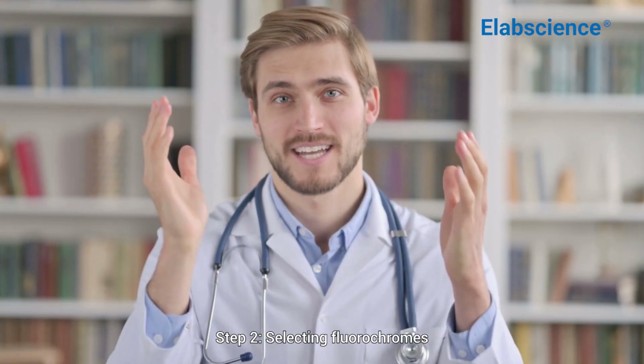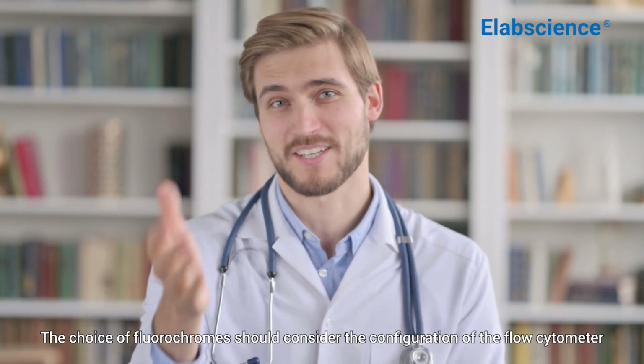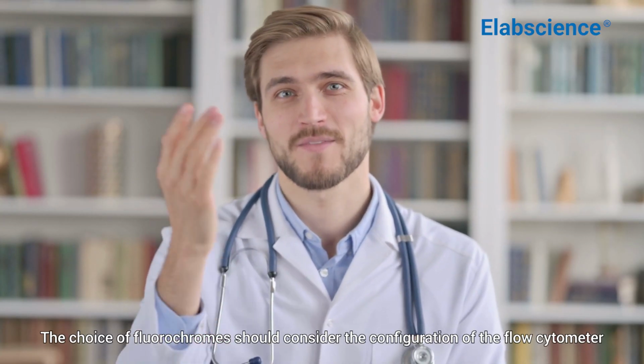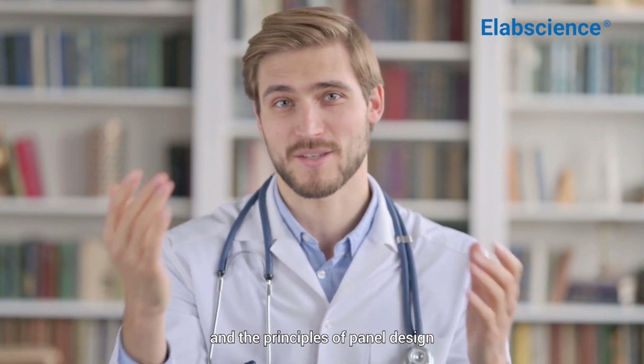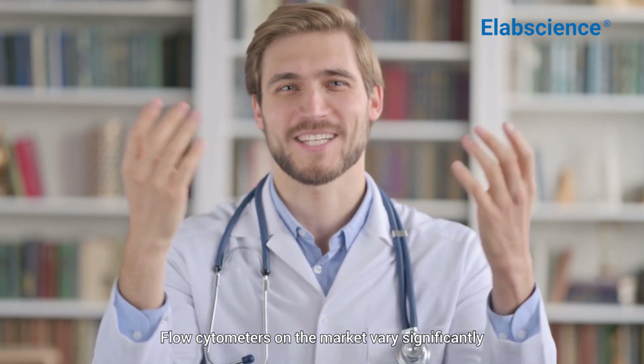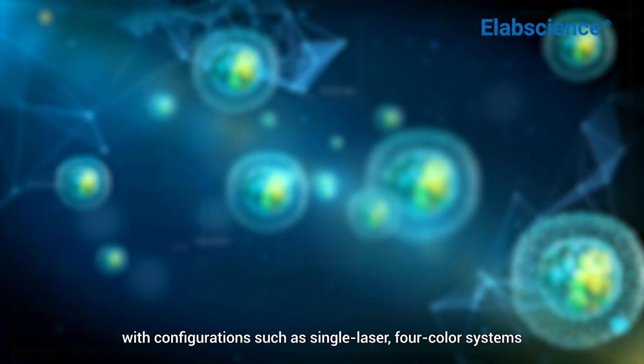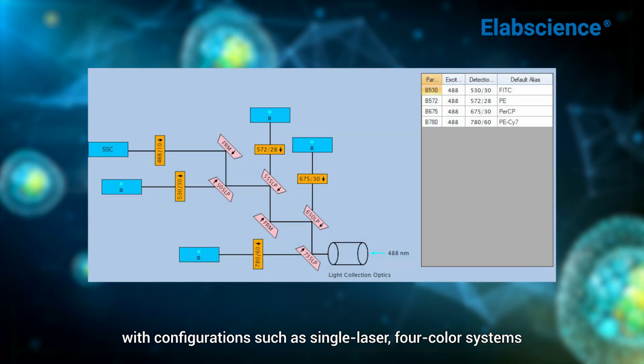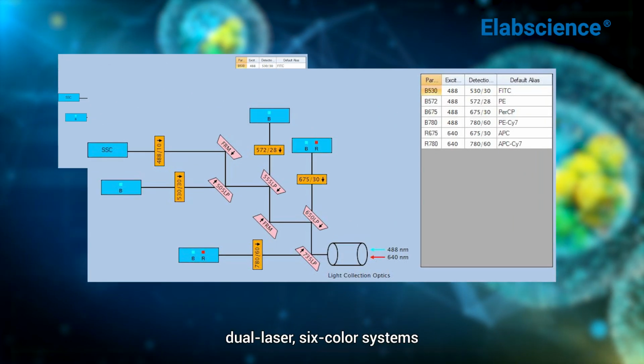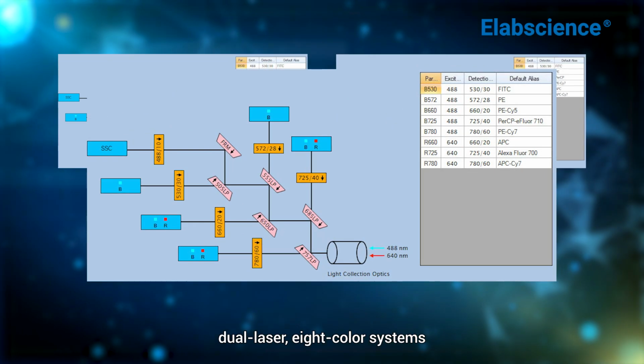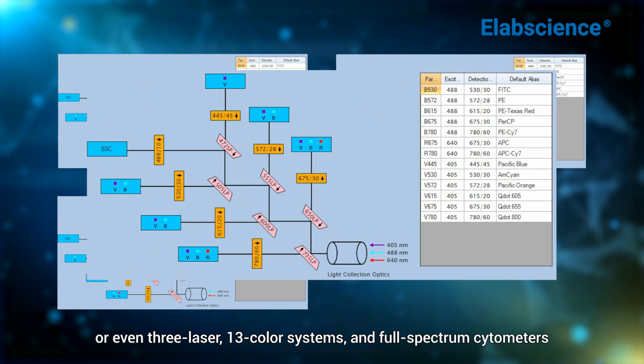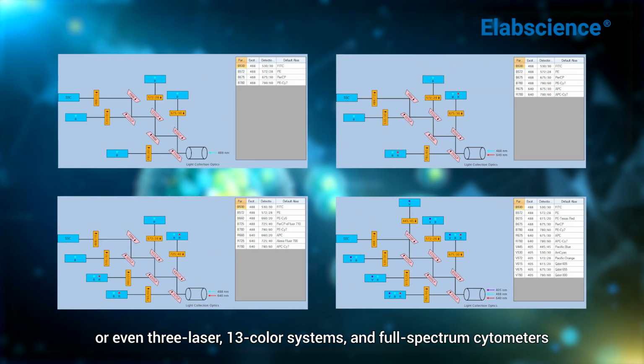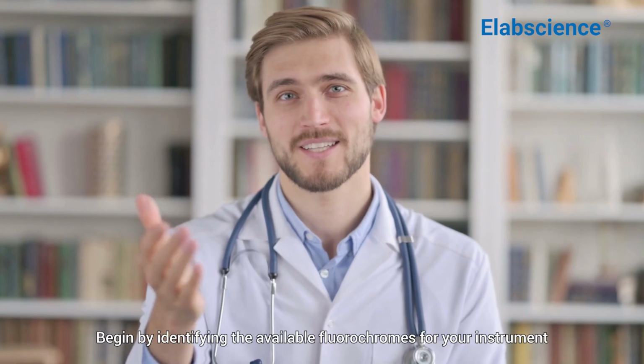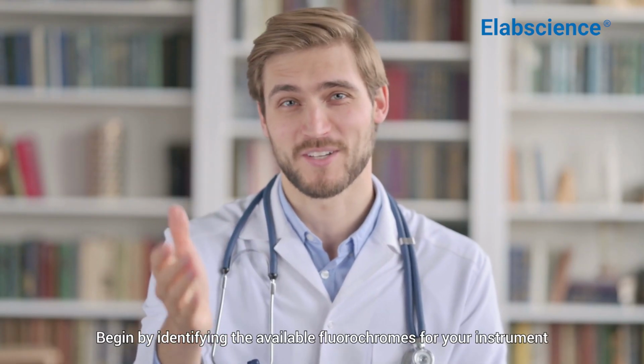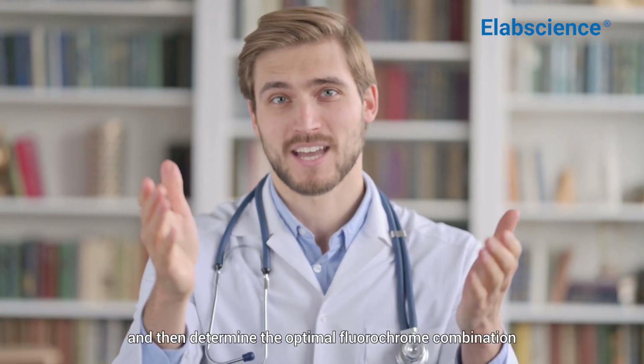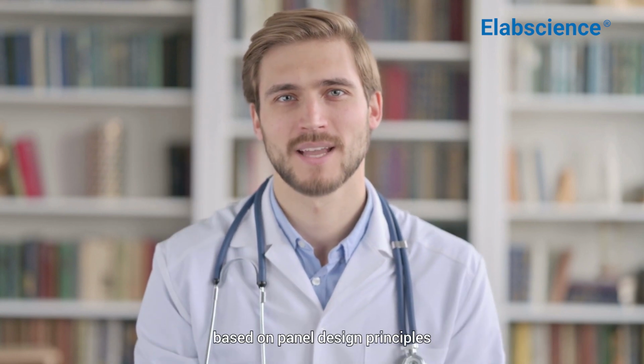Step 2. Selecting fluorochromes. The choice of fluorochromes should consider the configuration of the flow cytometer and the principles of panel design. Flow cytometers on the market vary significantly, with configurations such as single laser, 4-color systems, dual laser, 6-color systems, dual laser, 8-color systems, or even 3-laser, 13-color systems, and full-spectrum cytometers.